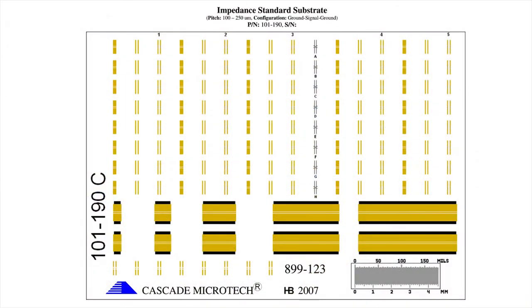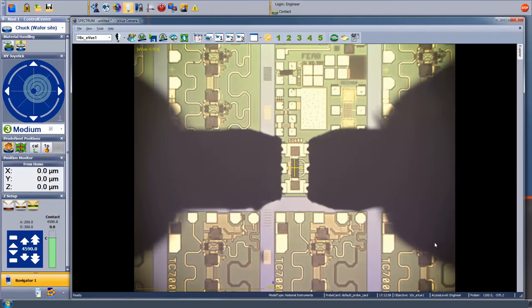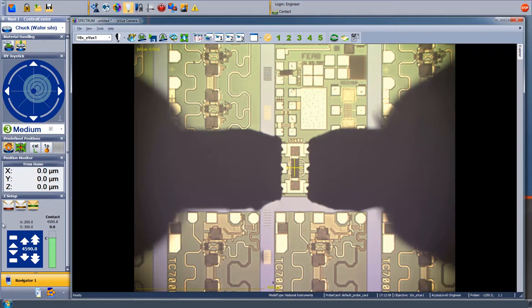We do this using an impedance standard substrate, or ISS for short. This has known impedance structures like short to ground, 50 ohms, and through lines of various lengths. Our prober station already has one loaded at the upper right corner of the chuck.